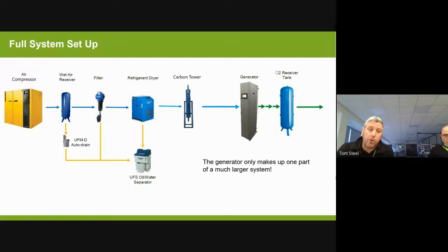We've also got a refrigeration dryer. This will have filters inside it as well that have to be replaced, and it's all about just maintaining the system. Everything that comes from the wet air receiver on the auto drain or the filter with the auto drain attached, and the refrigeration dryer, will have to go into, if it's an oil compressor, an oil water separator, because it's a condensate drain that comes from these things. You can't put it down the drain because it's got oil in it, so we need to separate the oil and water so we have clean water we can get rid of, and we've got oil stored that we can correctly dispose of as per wherever you are and the local legislation.